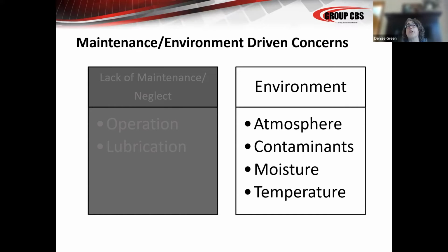So circuit breakers that are in very high temperature environments will have their lubricant come to the end of its working life a lot sooner than equipment that's in a more climate controlled environment. The opposite happens when the temperature is very, very cold. Grease products that are in the breaker as lubricants tend to get thicker and stiffer. So you might not have a breaker open physically as quickly as it should when it's in a very, very cold environment.